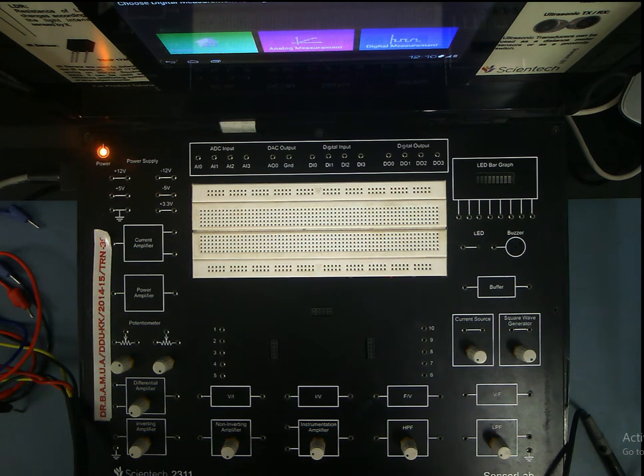Now it is another objective to translate that change in millivolt. So you have the temperature in terms of change in millivolt, and you have to take that change in millivolt to the respective value of temperature. So again you need to do some sort of electronic manipulation of the signal, so that you can exactly know what is the temperature through the thermocouple.